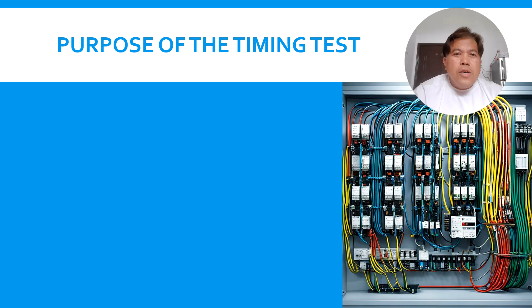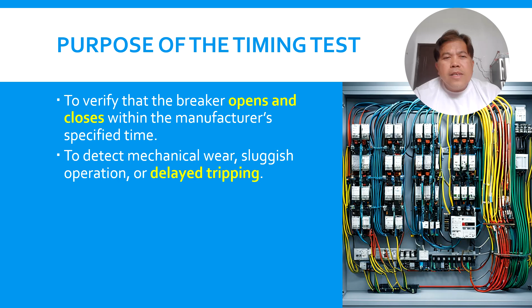So the purpose of this timing test is to verify the breaker opens and closes within the manufacturer-specified time. There is always a data sheet from the vendor or manufacturer required for your particular project, so there is always a specific timing. But basically, it is almost the same, even across different companies: it opens and closes within a specified timing. It is also to detect mechanical and electrical operation problems and tripping delays, and to confirm proper coordination with the protection relay. This is very important, guys. That's why we have a protection coordination study, to ensure clearing of the safety system.